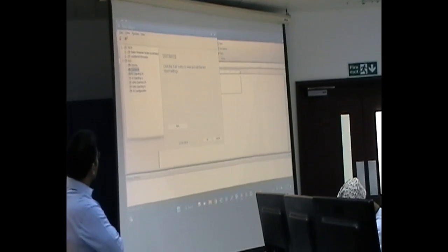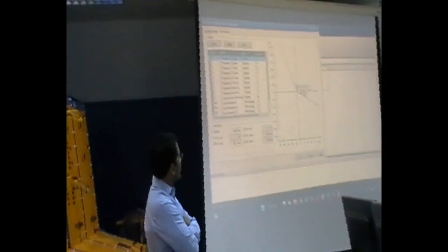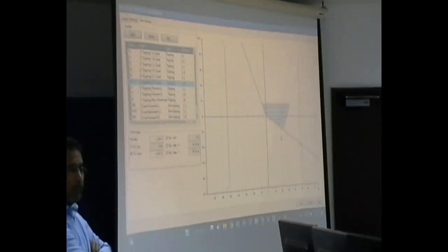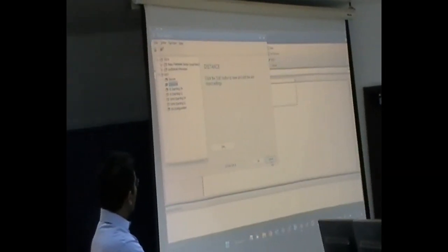Now the Omicron also has the ability to show you the characteristic of the relay. So zone 1 is highlighted here, and zone 2 is highlighted here, and zone 3. Maximum 2%. This is the highest. So now here is only the setting. I haven't started any testing yet, but at least now I can confirm that whatever I imported from the relay is exactly the same as the setting in the relay. Otherwise, while we are testing, it will give us wrong results. So we'll start the testing.